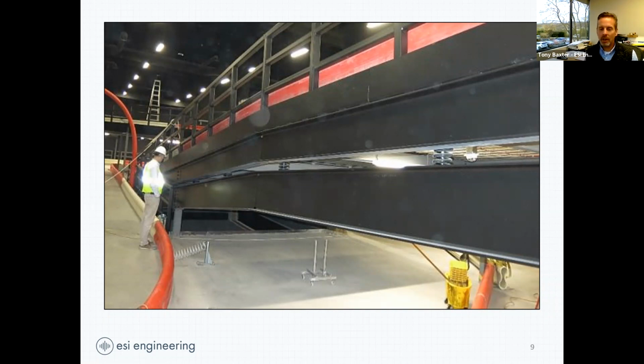So the vibration was high enough when we drove it onto the floor before this was done, just in our testing, in that retail space down below, the ceiling grid was shaking. It was a fairly smooth floor, but the ceiling grid was shaking. There was some other display stuff with plastic plants, and you could just see the leaves shake. The lights were shaking, and you could hear the noise.